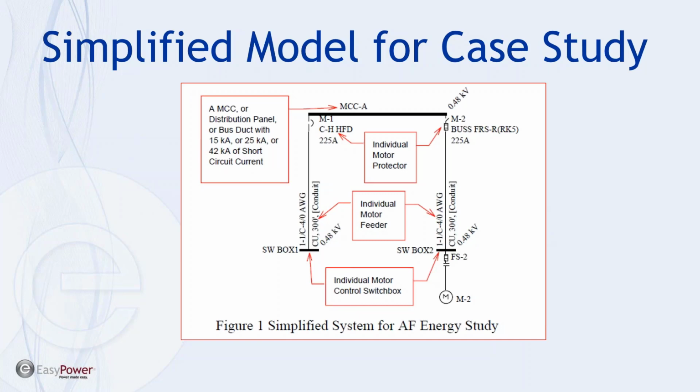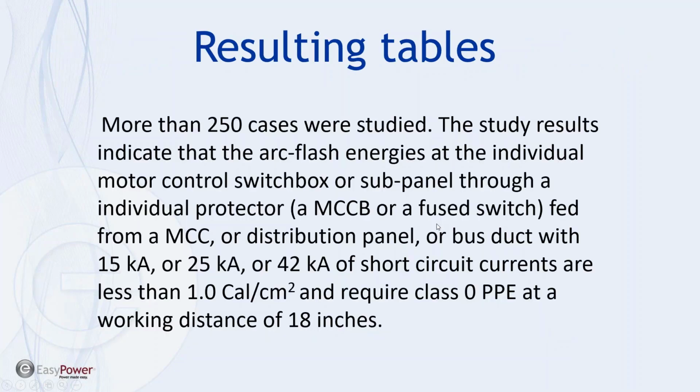Now, the reason for showing this to you is that this study and the methodology here, I think, was rather clever, but it reduced the cost of doing the study by a considerable amount, primarily in the form of data collection. Again, because it involved a lot of equipment on their part and a lot of downtime to be able to collect the data that we were considering. So once we set up the simplified circuit in EasyPower, we were able to change all the variables and then plot the results.